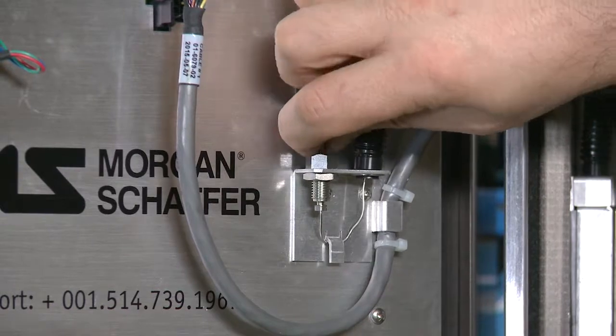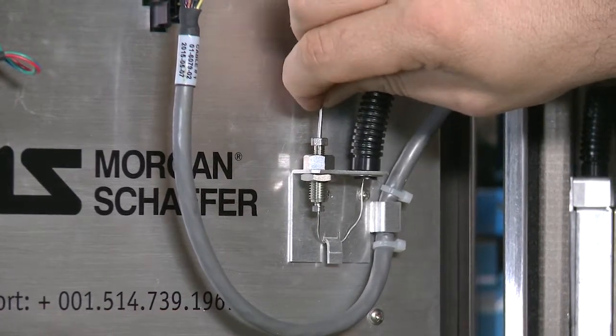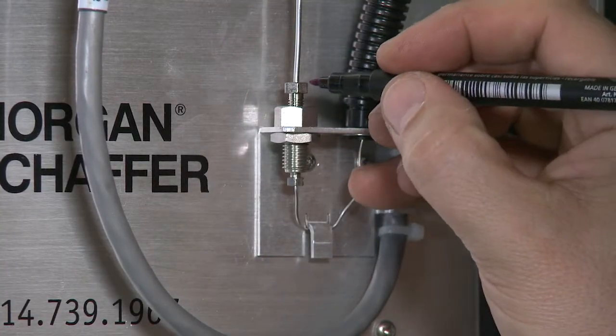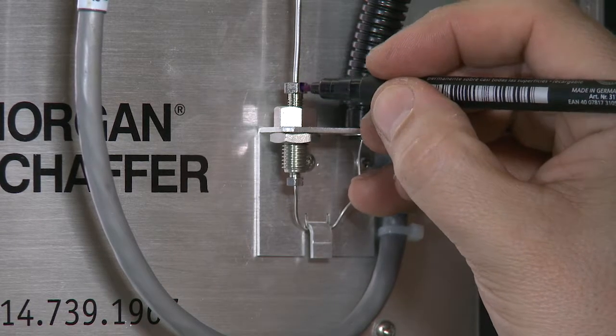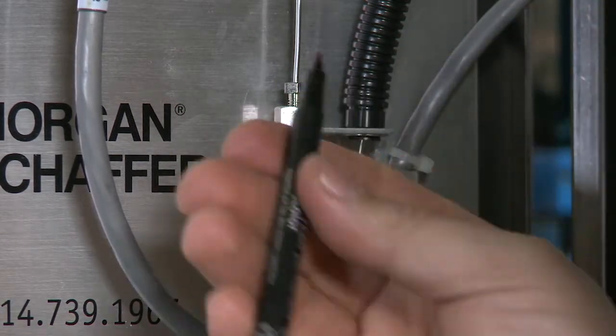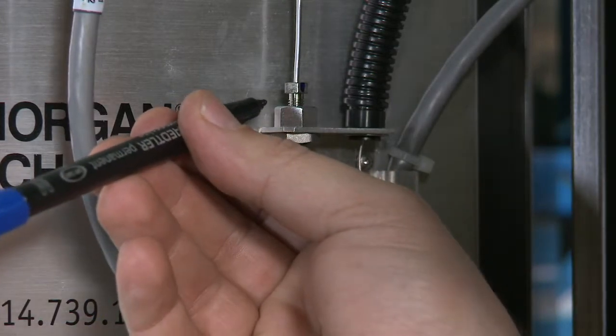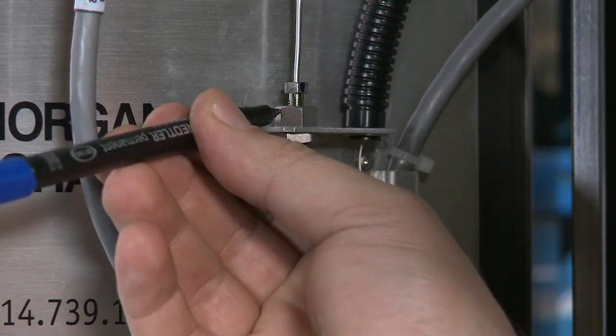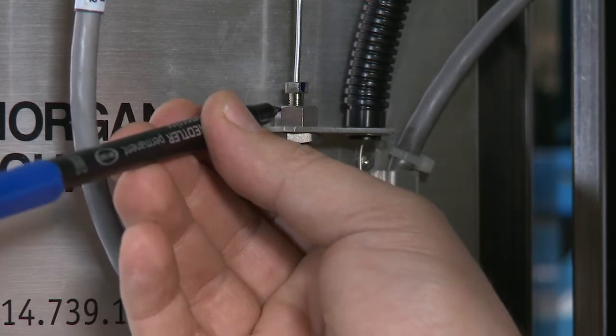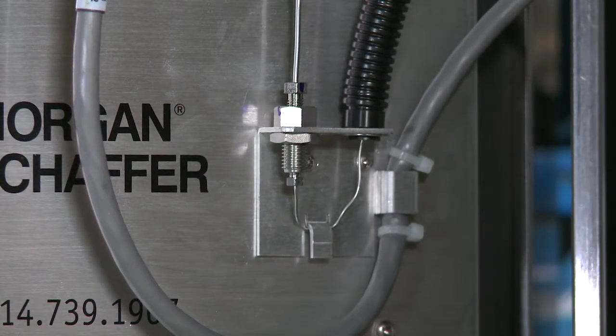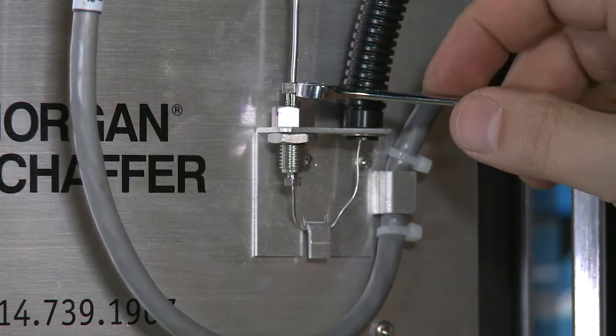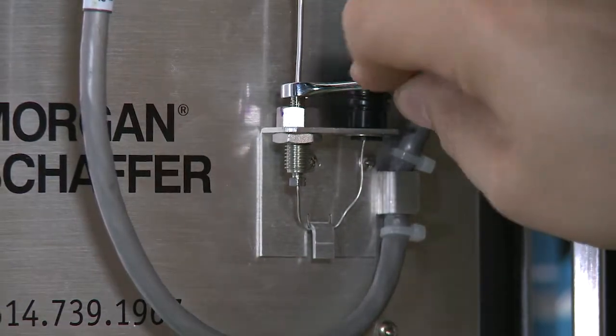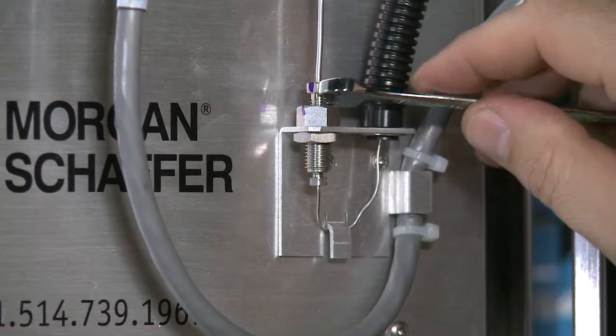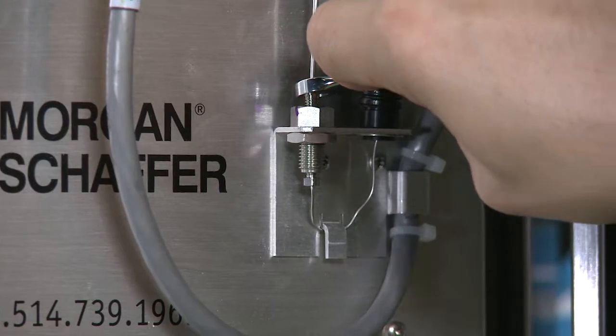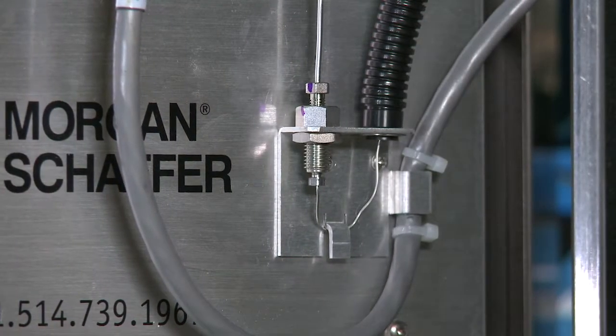Finger tighten the tube nut to the reducing fitting of the door. Swage the 1/16" calibration gas tube onto the tube fitting by using one of the two following methods. The recommended method is to use a 1/4" open-end torque wrench set at 34 pound-force per inch. If there is no torque wrench available, the alternative tightening method is to perform a finger tight on the screw first and do a 1/4 turn more with a 1/4" open-end wrench.